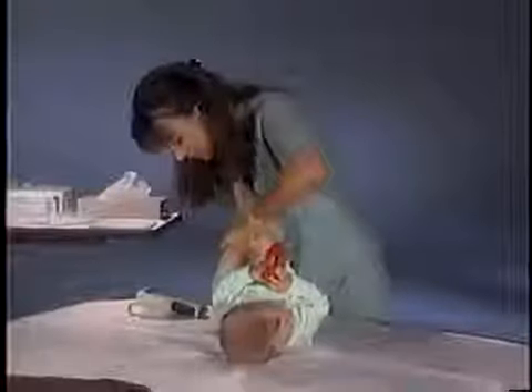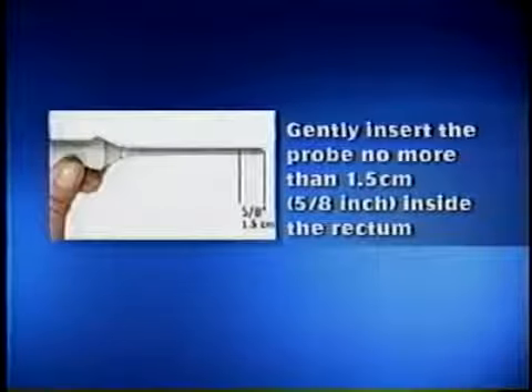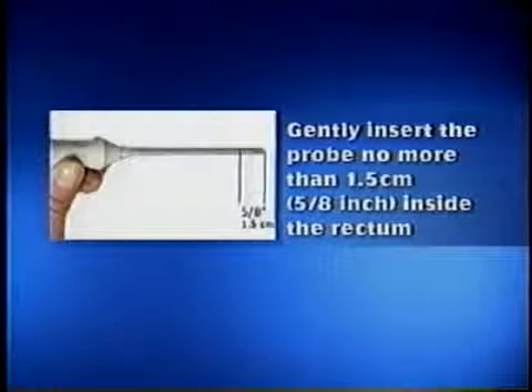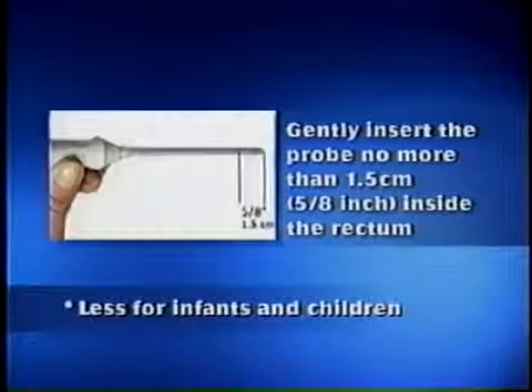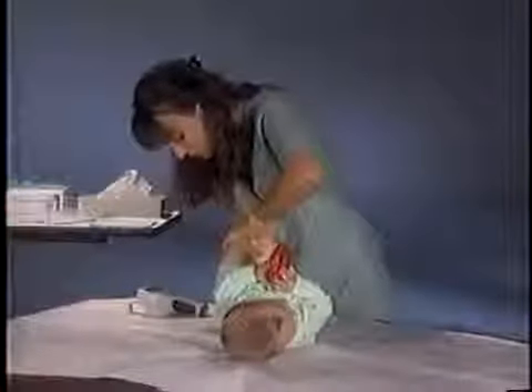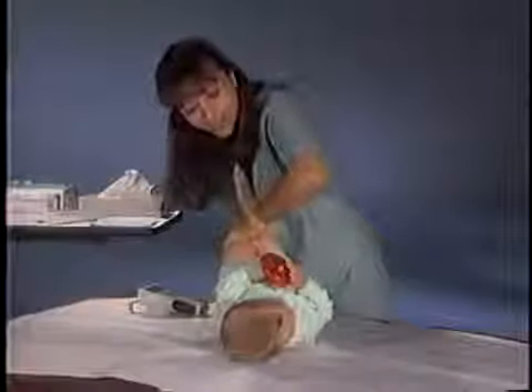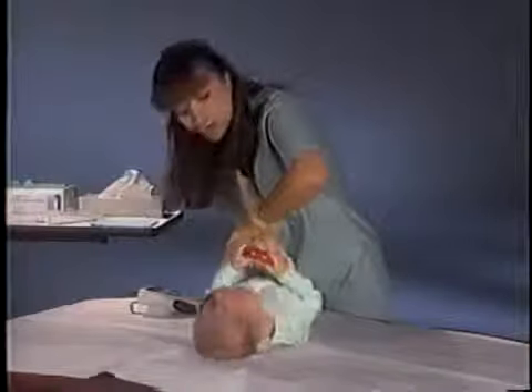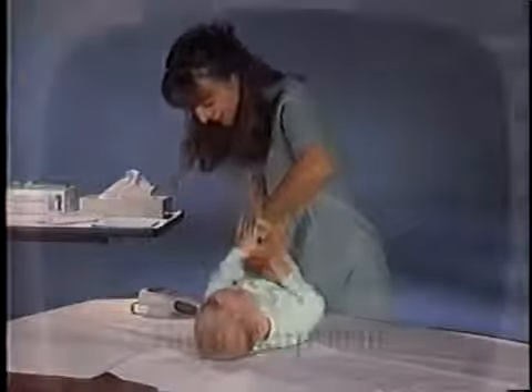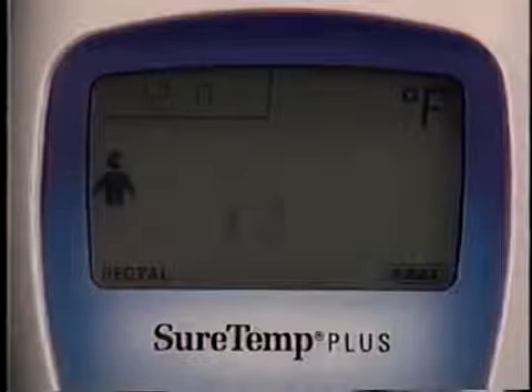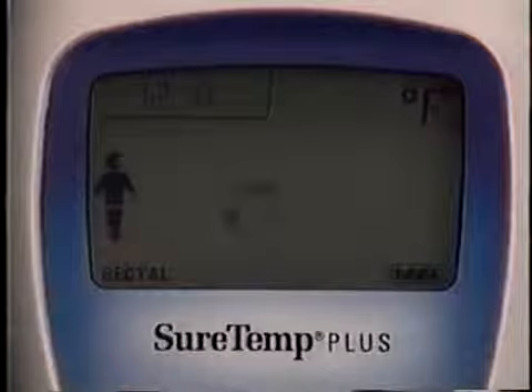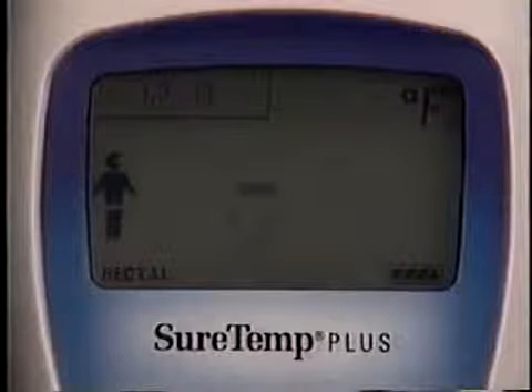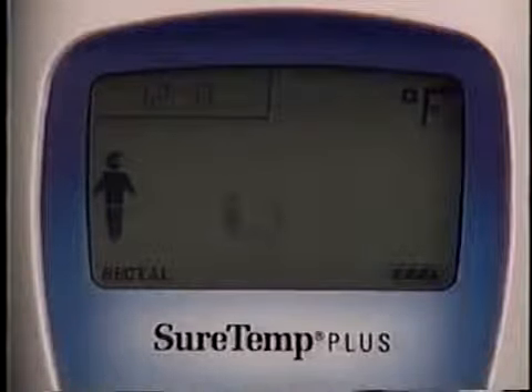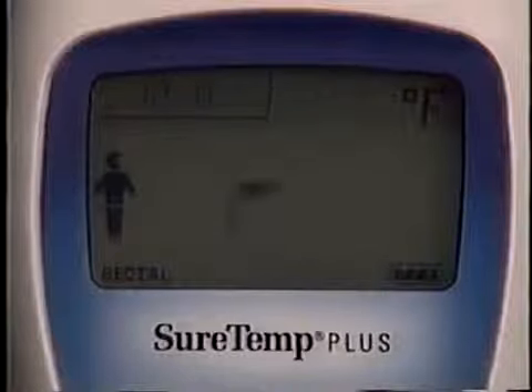Gently insert the probe no more than 1.5 centimeters or 5/8 of an inch inside the rectum, less for infants and children. Hold the probe in place throughout the entire measurement, keeping the thermometer and probe cord away from patient contact. Walking segments appear on the display. When the final rectal temperature has been reached in approximately 10 seconds, the unit beeps and the temperature displays.